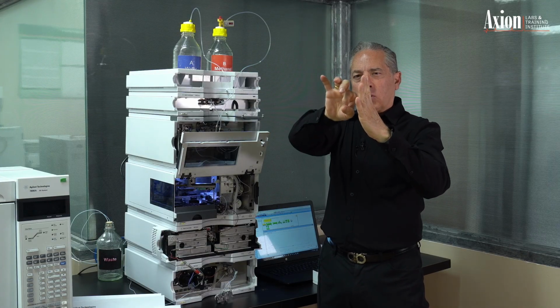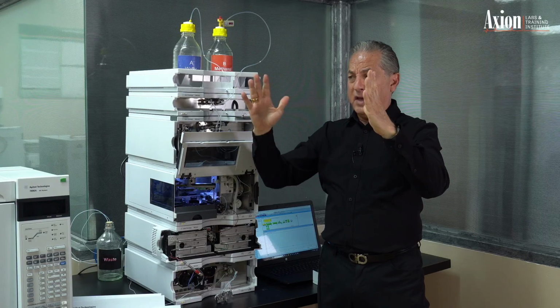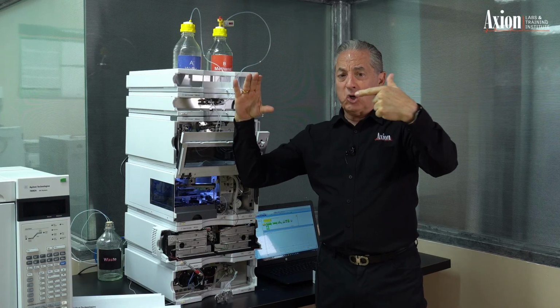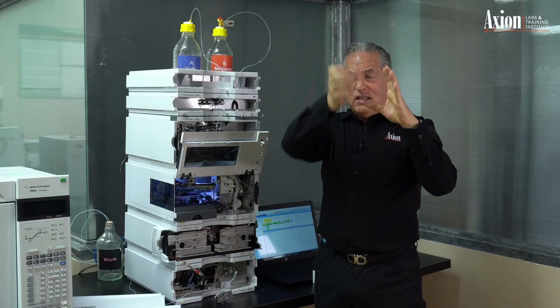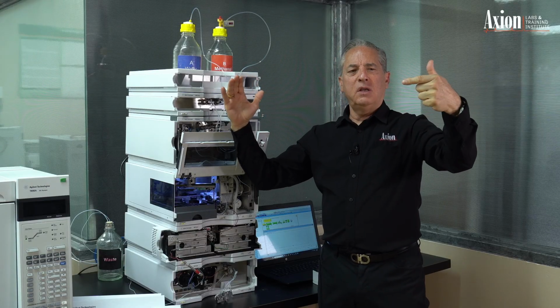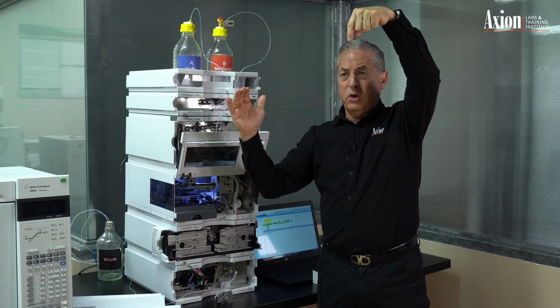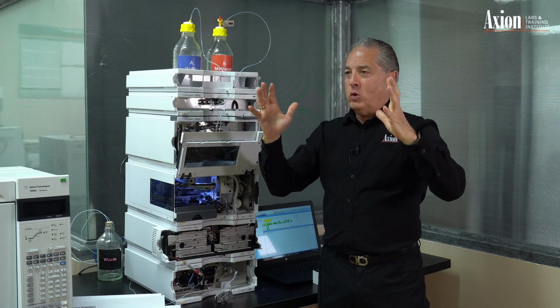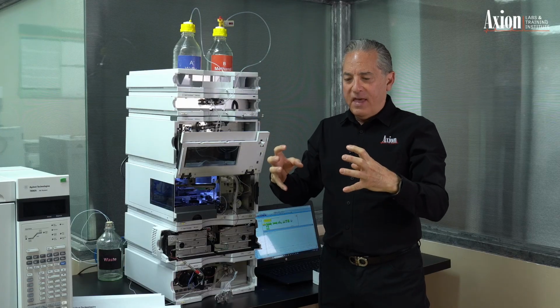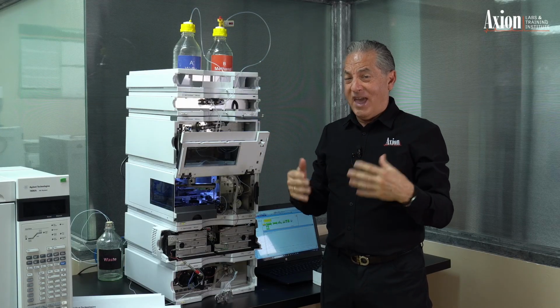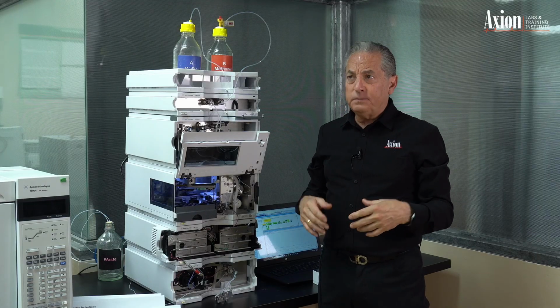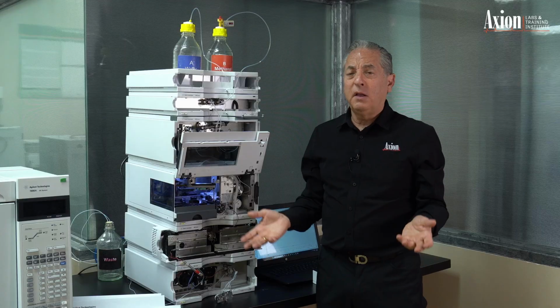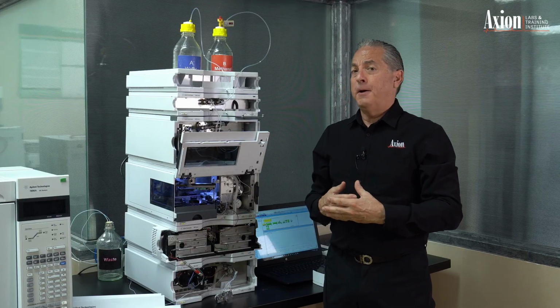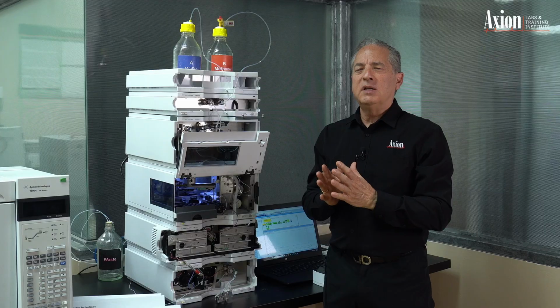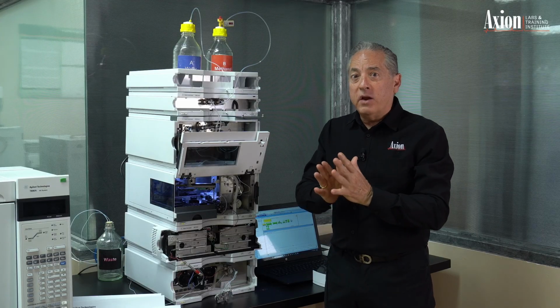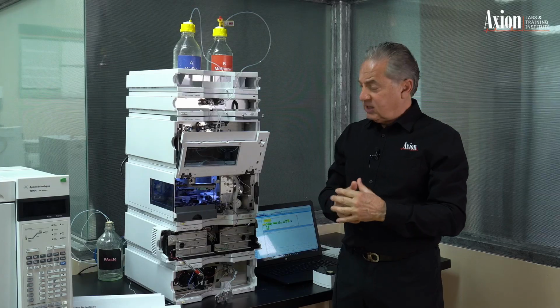The flow comes in the top, goes down the path, and then goes out to waste. So we shine light in here. We measure how much light is absorbed by the sample. This Z flow is useful because if we measure in the direction of flow, we get less noise. We don't like to measure across the flow. So this essentially is a cuvette, a flow cell that allows us to measure the absorbance of light of the analytes running through. Now these flow cells are very small. 13 microliters is a standard flow cell. You can easily get a half microliter flow cell and get smaller if you need, but they're very small, which means they introduce very little broadening or very little loss of efficiency in the instrument.